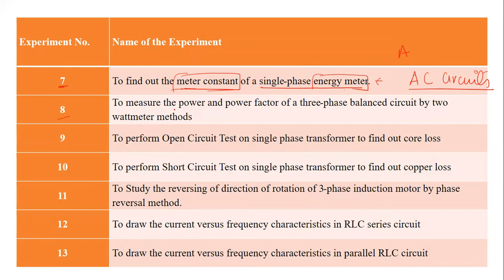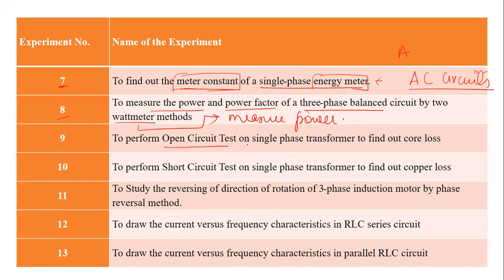In experiment number eight, we will understand what power is, how to measure it, what is power factor, and how to measure the power factor practically for a three-phase balanced circuit using a watt meter. Watt meters are instruments used to measure power. Then we understand how to perform the open circuit test on a transformer to measure the iron losses or core losses, and also the short circuit test to measure the copper losses, also known as winding losses.